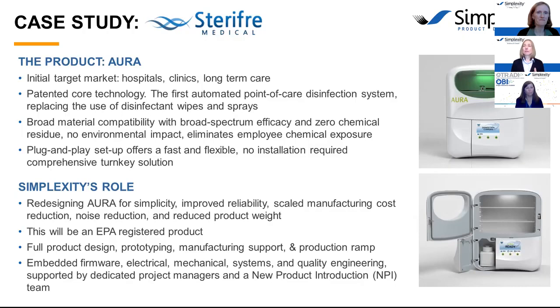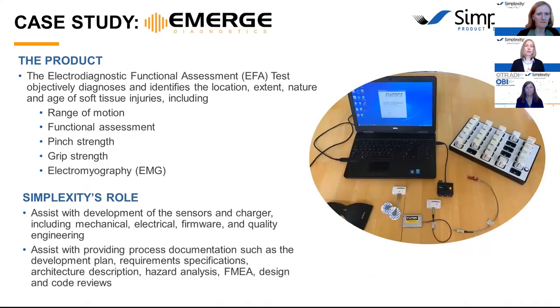And this is an embedded firmware project. So basically this device is not connected, and we don't have a whole layer of software, which sometimes we have on products. Basically it's a standalone unit. And so the firmware development on this is looking at how all the different aspects are controlled, monitoring door switches and sensors, looking at the screen, what's displayed to the user, looking at how much hydrogen peroxide is left in the unit and having indicators and so forth. And all of that is displayed on the screen. So the user puts the items in, closes the door, presses the button, and the system starts up. And so that's all contained, and we're working on, again, what are all the possible errors and how do we fail safe this product. And then we'll talk about one more, and then at the end, again, we can get into Q&A on these.